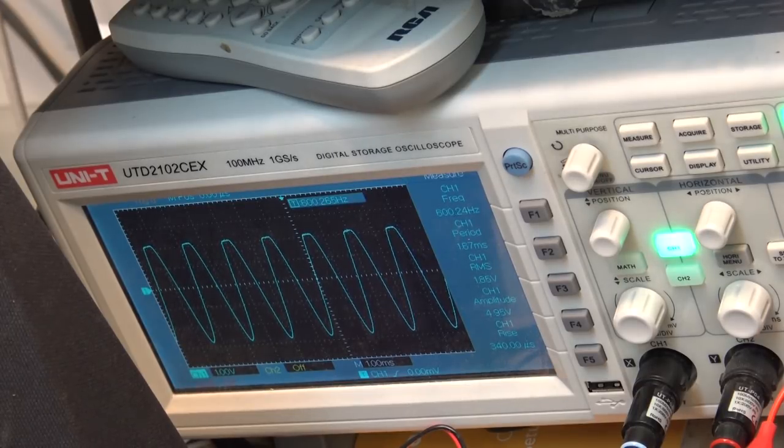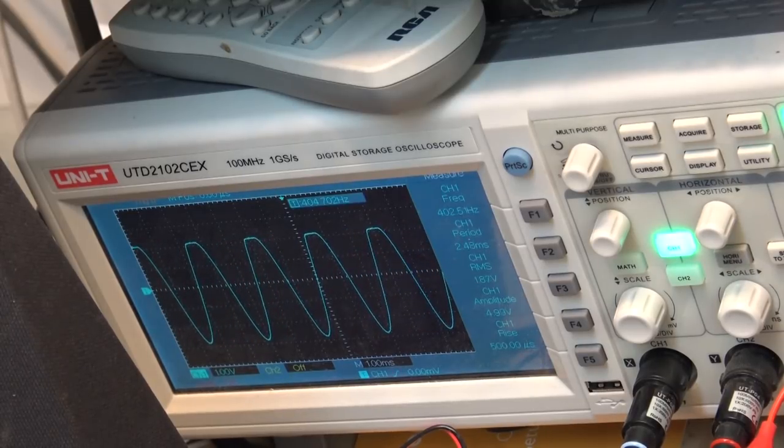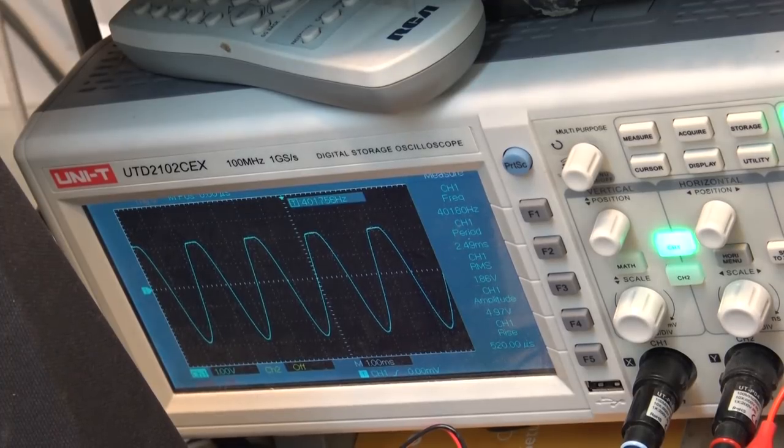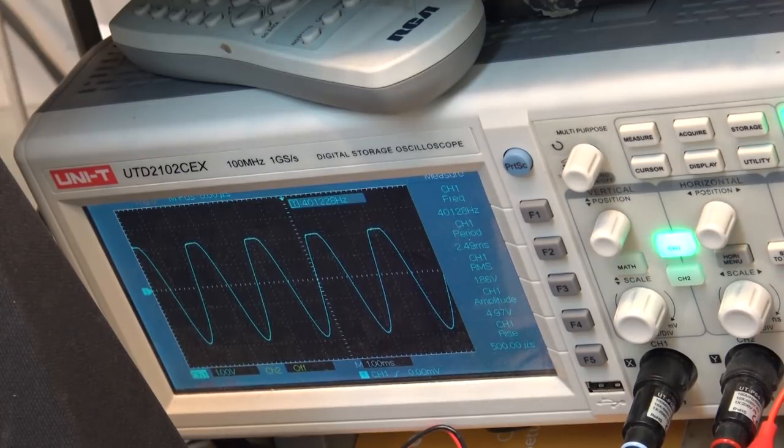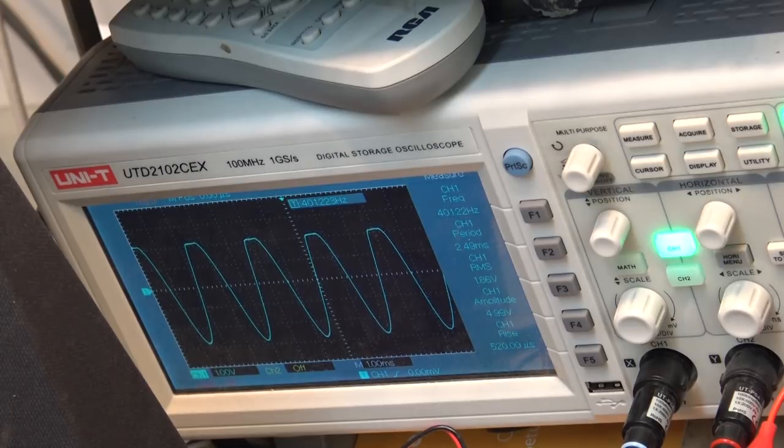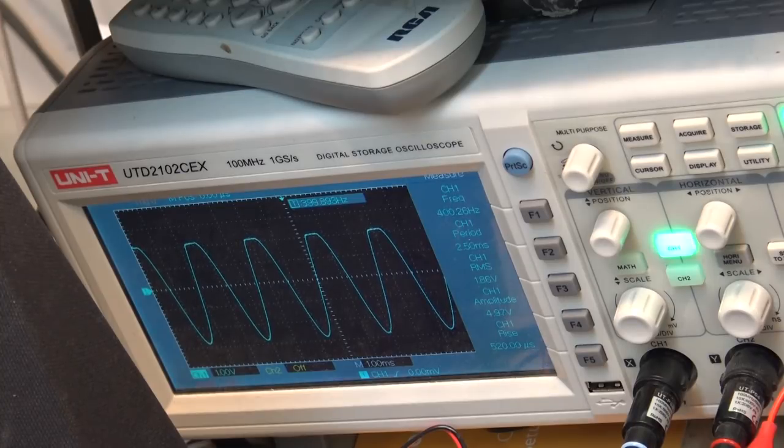Notice that the top of the waveform is a little bit flat and that's a problem with the unit that I'm going to have to resolve before I can get this thing properly calibrated. Should be right at 400 now. Pretty darn close, 401. There we go.